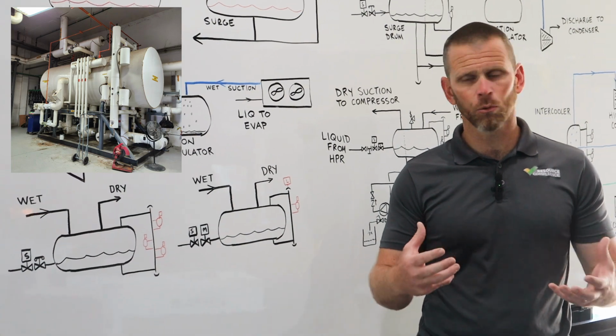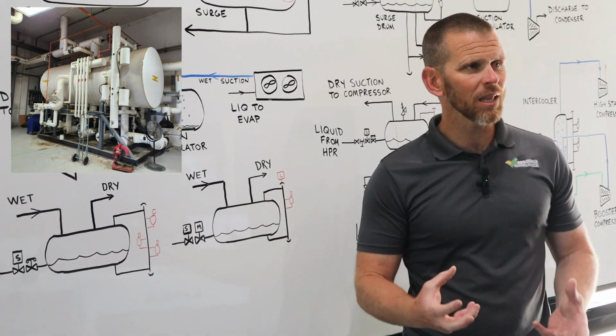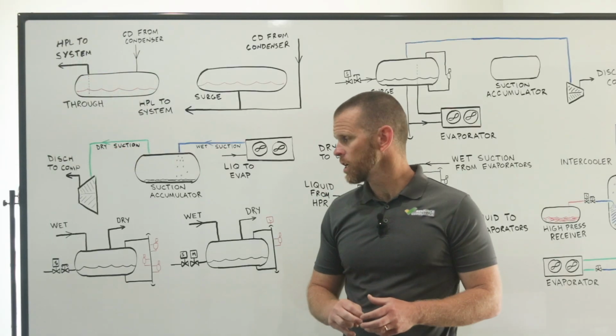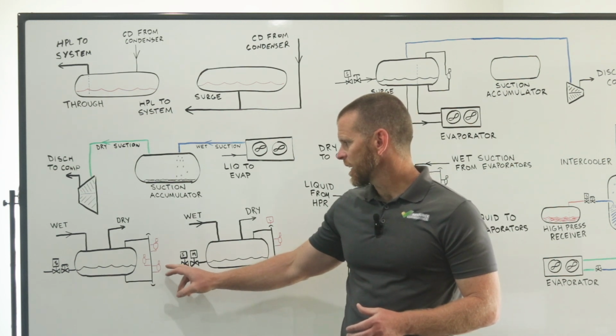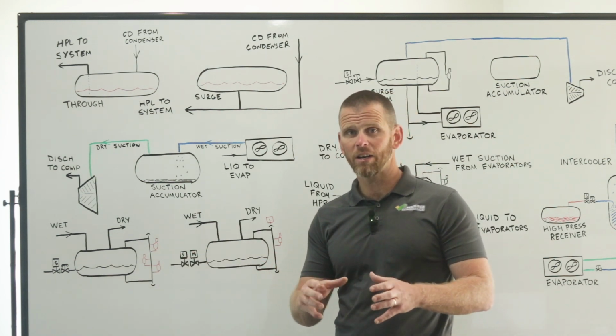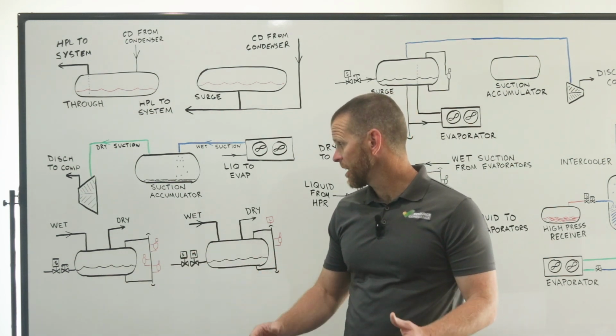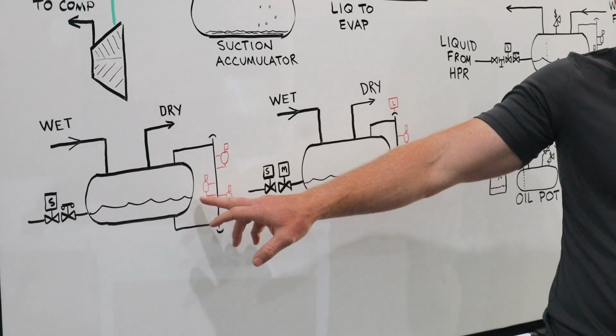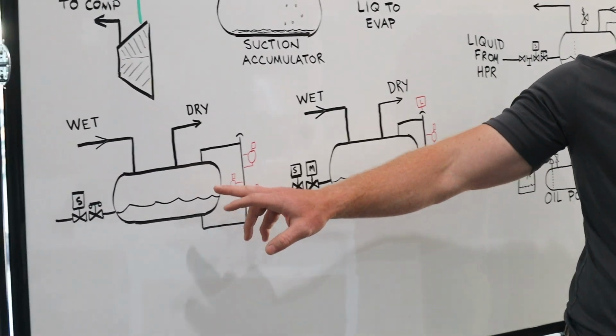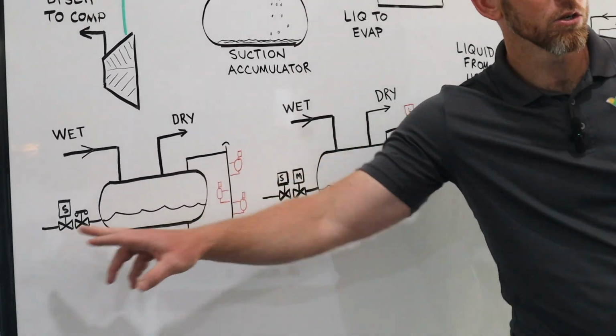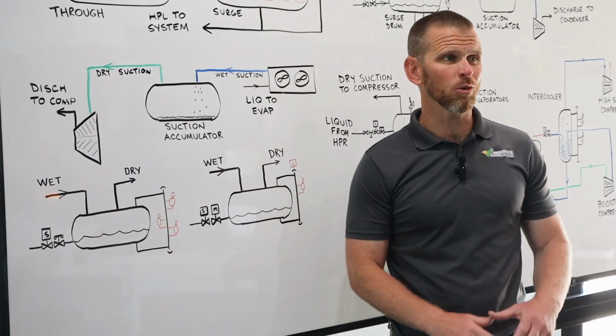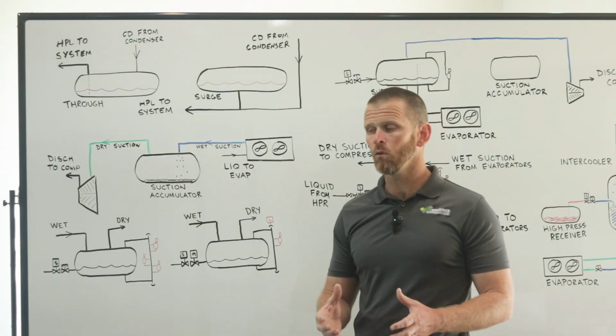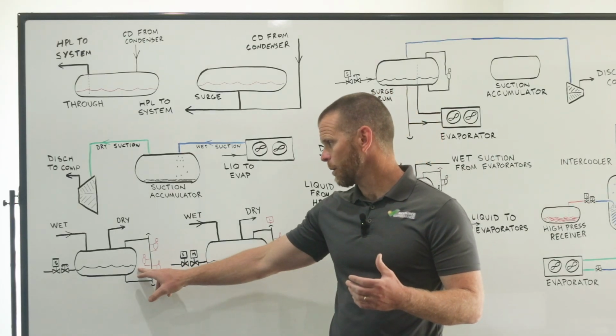It's equipped with 3 float switches. Typically, these would be like a ball float switch, and they're each interlocked with this recirculator to perform a function. It may be that this middle one would be most commonly interlocked with a solenoid valve to control the level inside the vessel. We might call that an operating level float switch. That's what that one is.